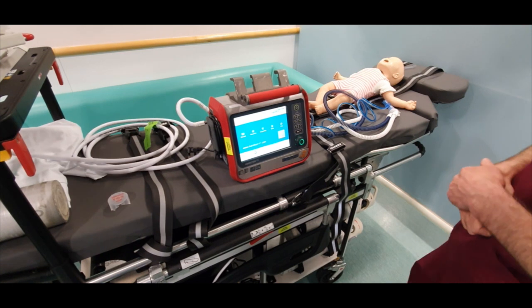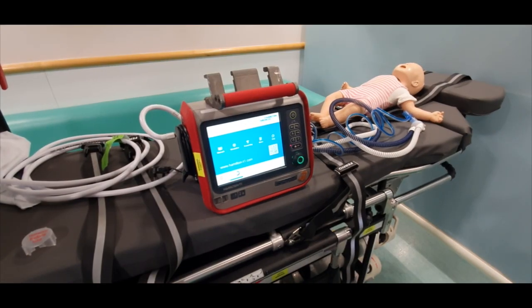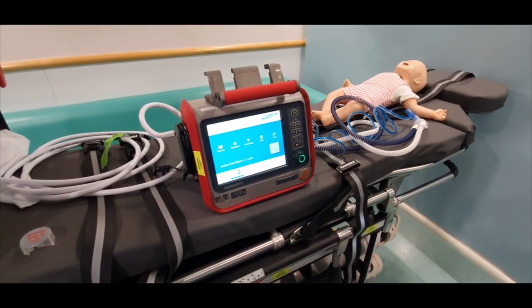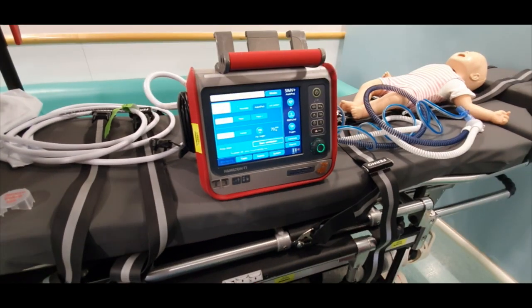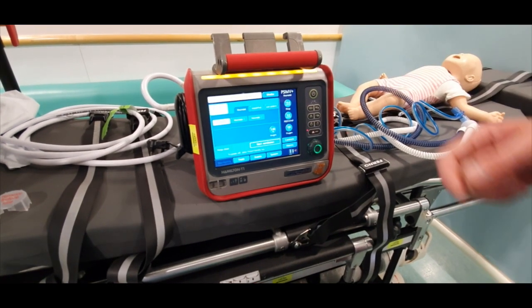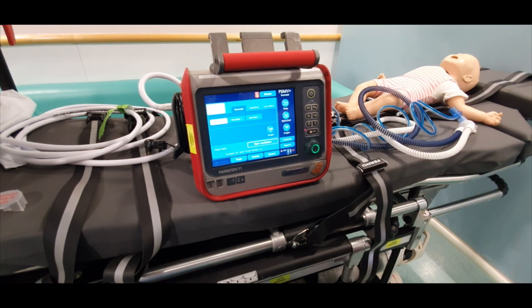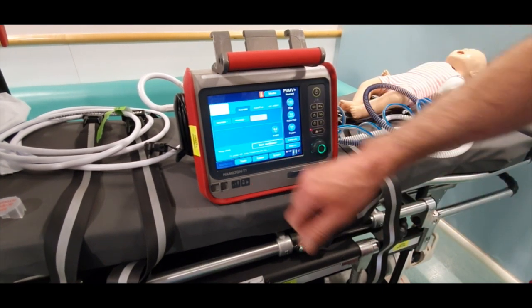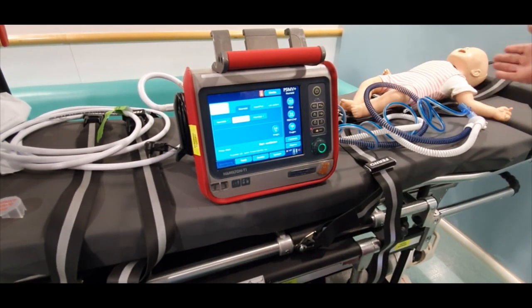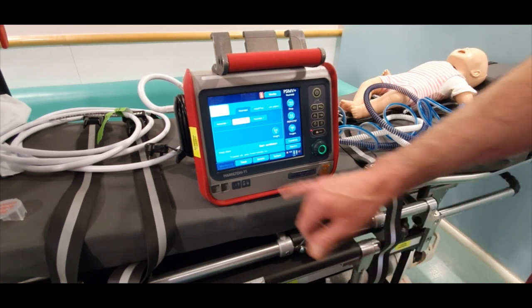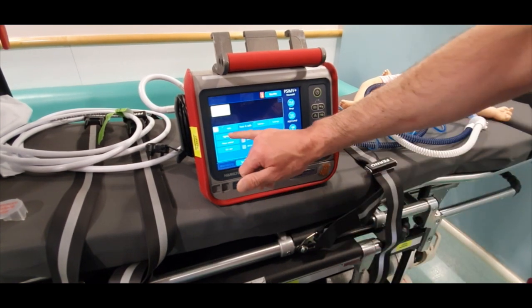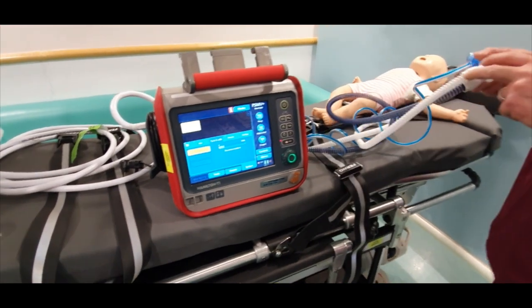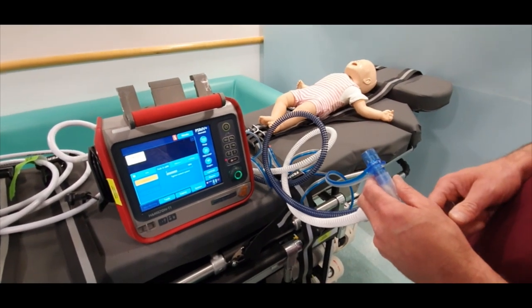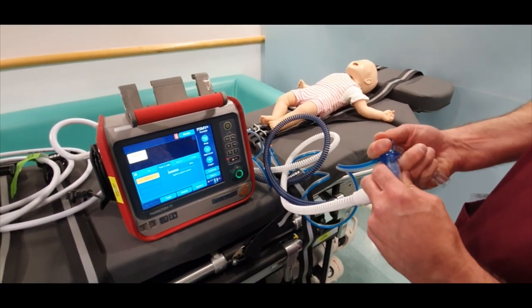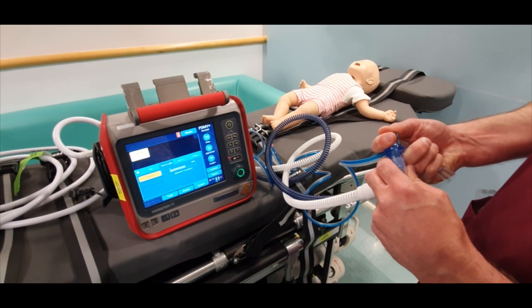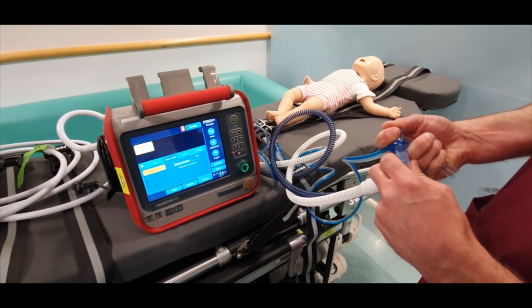Next, the ventilator is turned on and calibrated. The ventilator will recognise that a paediatric circuit has been installed and will therefore show wrong expiratory valve until you switch to the neonatal presets as shown. Children above 10 kilograms can be ventilated with an adult circuit, and so select the adult/paediatric tab in this case. Here, Mike has initiated the leak test.